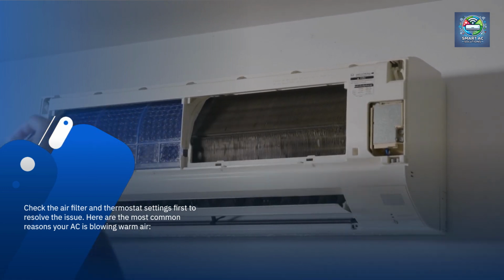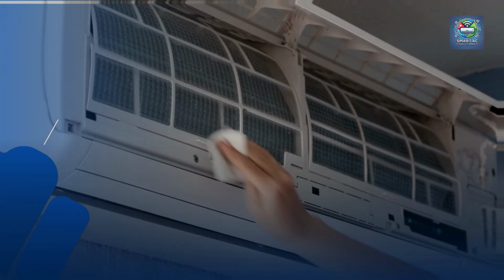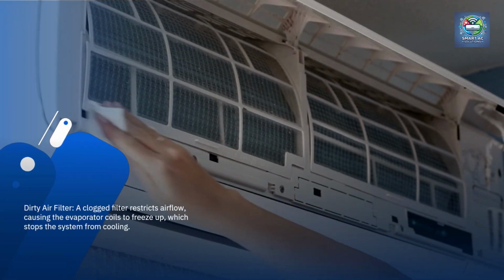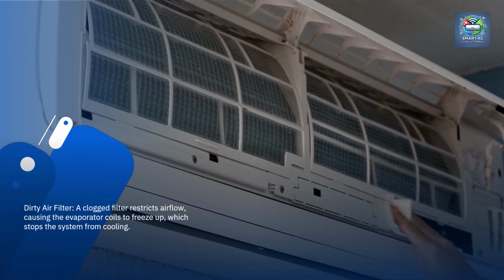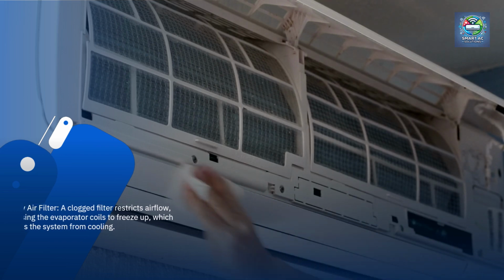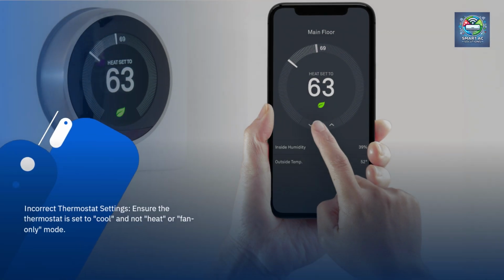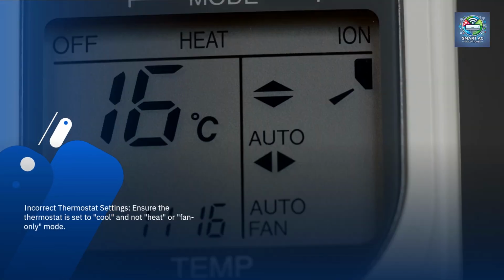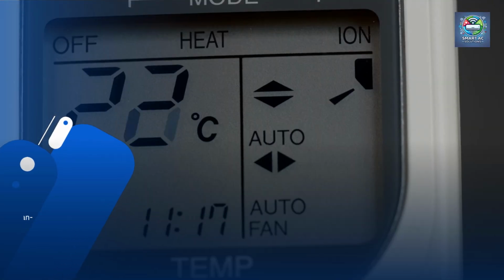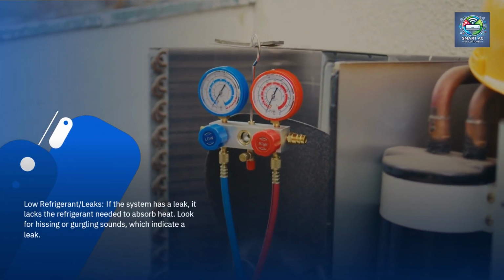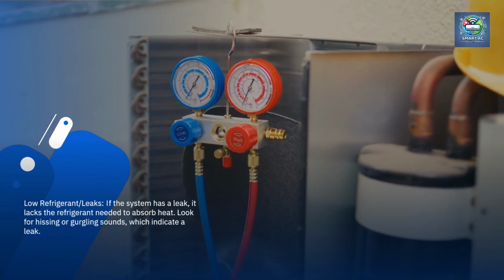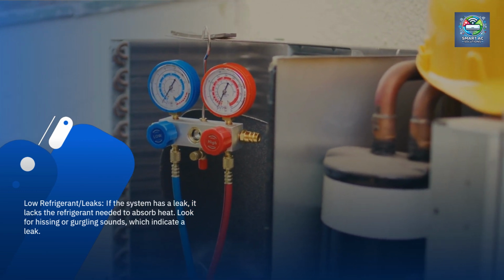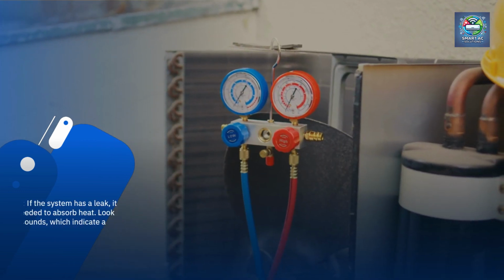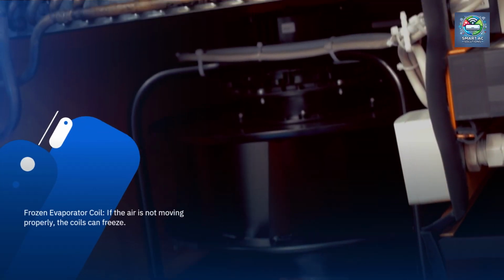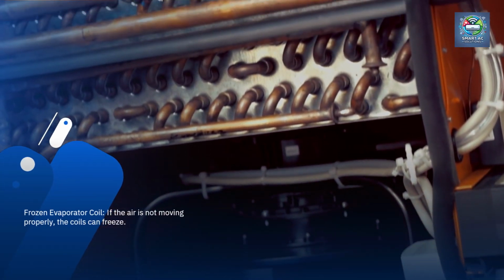Here are the most common reasons your AC is blowing warm air. Dirty air filter. A clogged filter restricts airflow, causing the evaporator coils to freeze up, which stops the system from cooling. Incorrect thermostat settings. Ensure the thermostat is set to cool and not heat or fan only mode. Low refrigerant/leaks. If the system has a leak, it lacks the refrigerant needed to absorb heat. Look for hissing or gurgling sounds, which indicate a leak. Frozen evaporator coil. If the air is not moving properly, the coils can freeze.